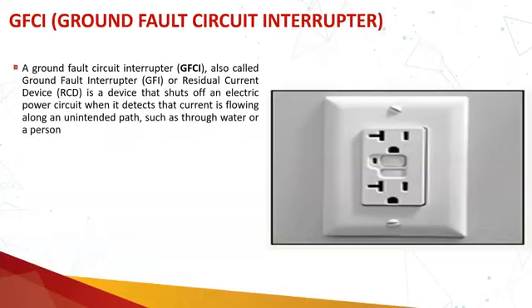So what is a GFCI? A ground fault circuit interrupter, also called a ground fault interrupter or residual current device, is a device that shuts off the electric power circuit when it detects current flowing along unintended paths such as water or a person.